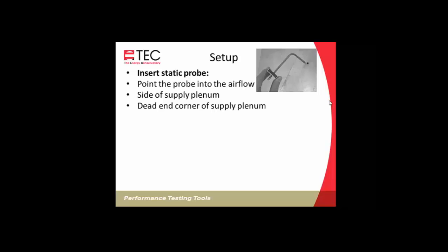And a dead end corner is defined as a corner that doesn't have duct or a trunk line or a register within 8 inches. So if none of those 3 things, a duct, a trunk, or a register are within 8 inches, then we'll have a pretty stable pressure there. We could put it on the side of a return plenum if that return plenum doesn't have a trunk line, a return register, or a return duct connected to it.